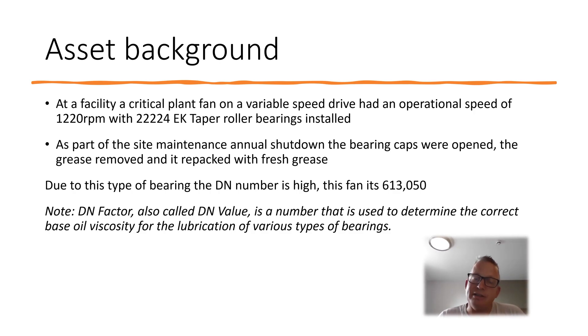One thing to take into account is the DN factor. The DN factor is the shaft mean diameter multiplied by the speed, then multiplied by another factor — for example, for taper roller bearings you multiply by three. This bearing has a really high DN factor and requires a really good quality grease so that when the bearing is working there is enough oil, soap, and viscosity in there to keep it working without skidding.